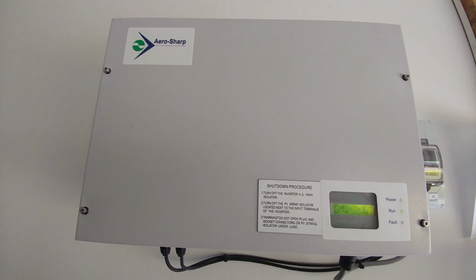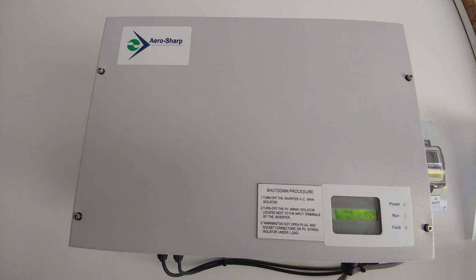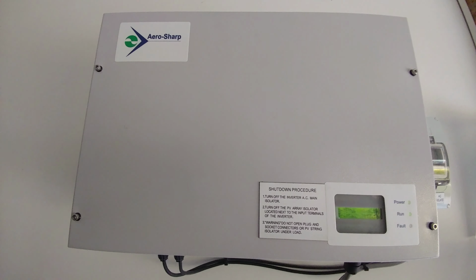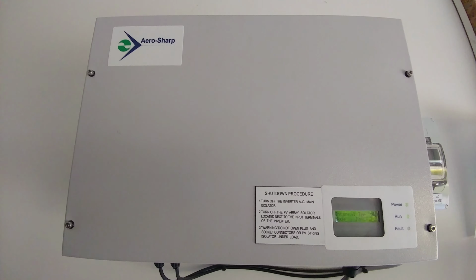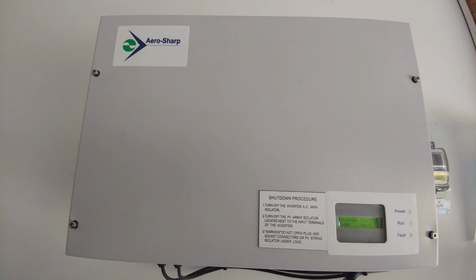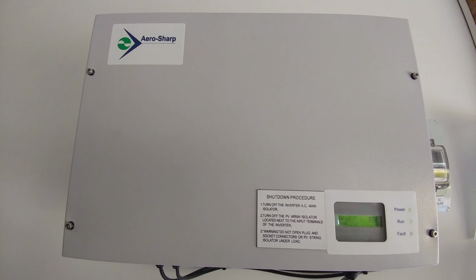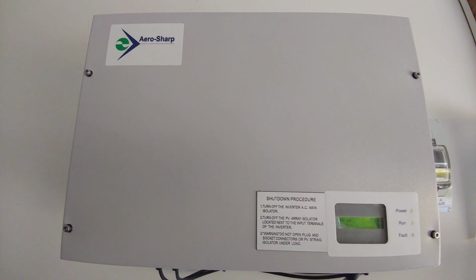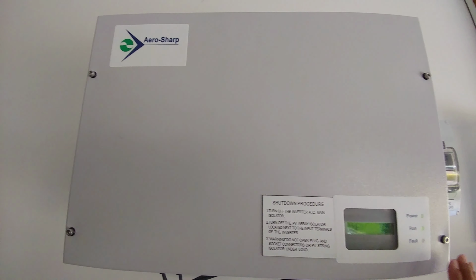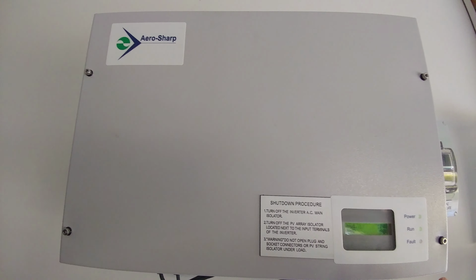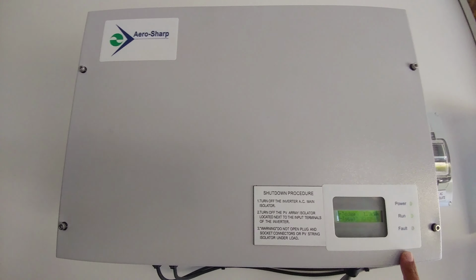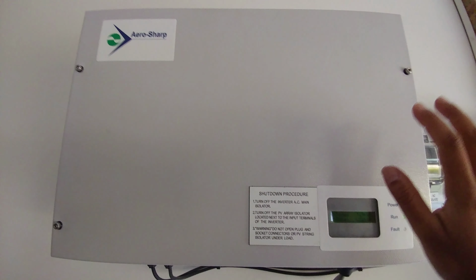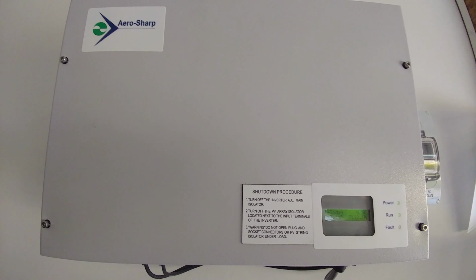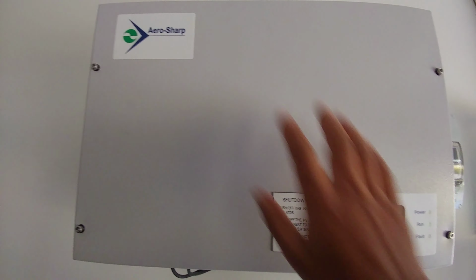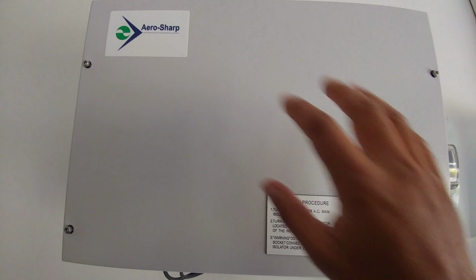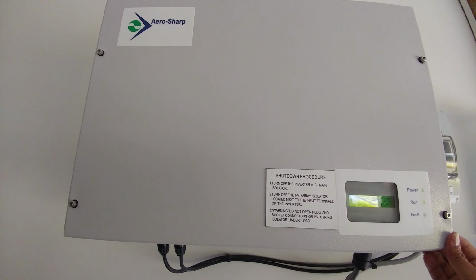Now, the reason why the cost is high also is because when this inverter was installed 9 years ago, there was no earth wire going to the solar panel. So when they put the new inverter in, if I had opted for that path, they would have to earth my solar panels. The reason for that is safety regulations. However, this unit got away with not having an earth for the solar panels because this is a fully isolated solar inverter. So it's got a big toroidal transformer in here. And this whole unit weighs about 40 kilograms.